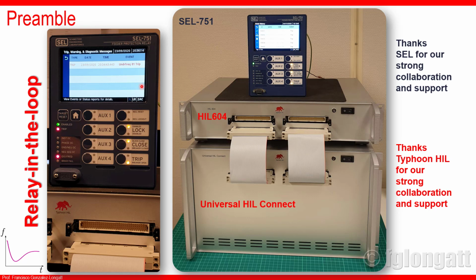In that moment, I was testing the under frequency protection function in this feeder relay, the 81, and I created the under frequency event using the real-time simulator, the Typhoon-HIL.